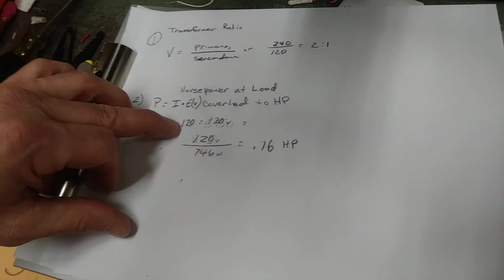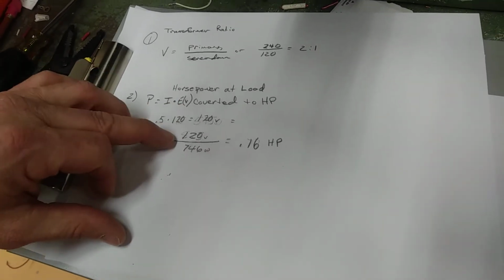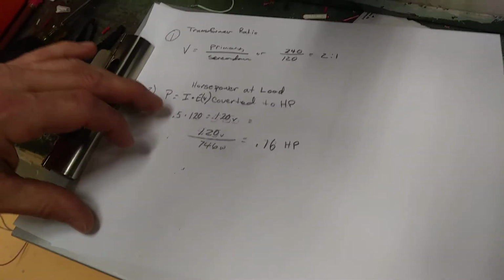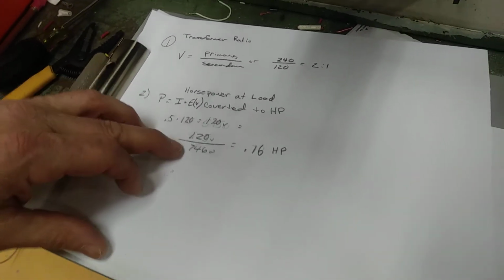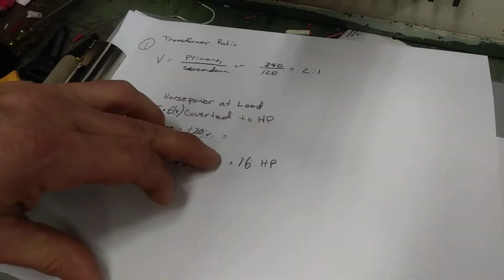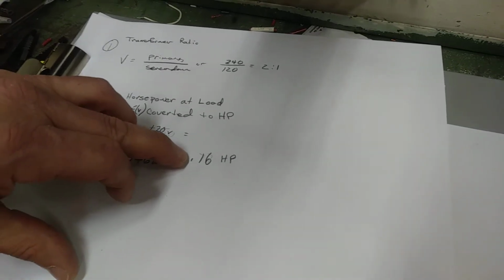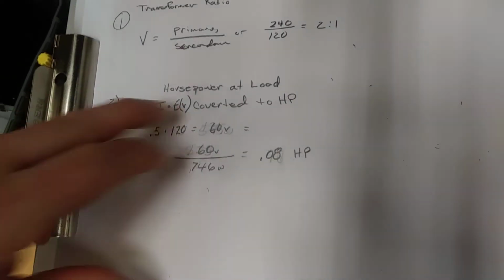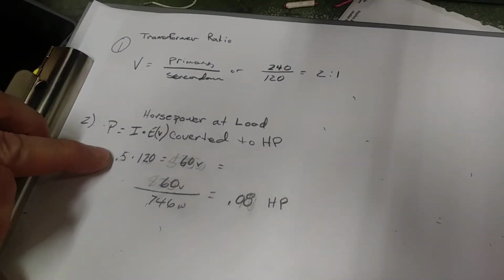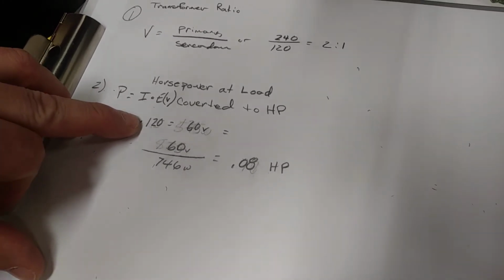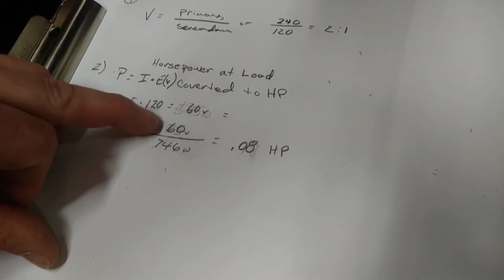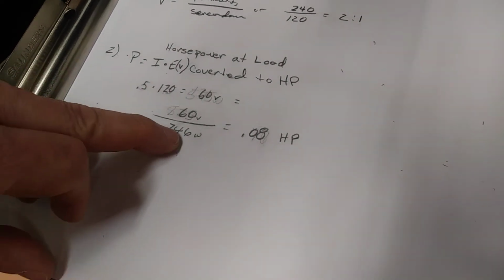We're calculating 0.5 amps times 120 volts, which gave us 60 watts. We took 60 and divided it by 746, which gave us 0.08 horsepower at the load, which represents the light.